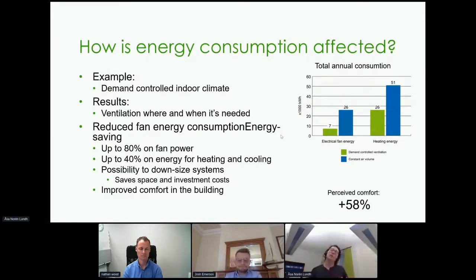But you can also look at it a different way: increasing ventilation when it's needed. If you already have an existing system, you can increase the ventilation rate when there is more occupancy, instead of reducing the air flow. So we can turn the argument around for why we should work with demand-controlled indoor climate - we should increase ventilation capacity when there are a lot of people in the office.